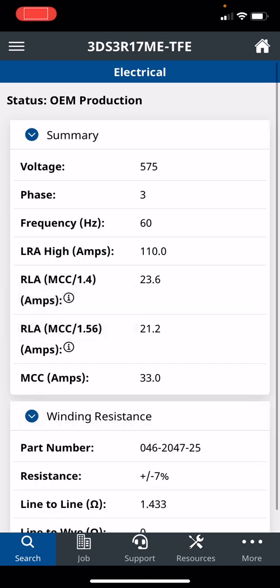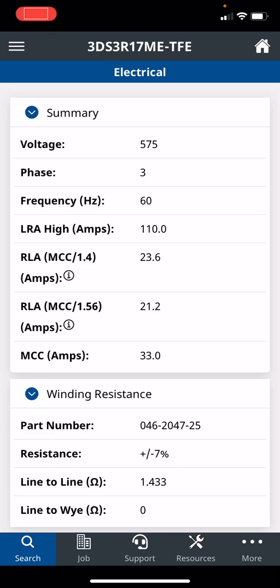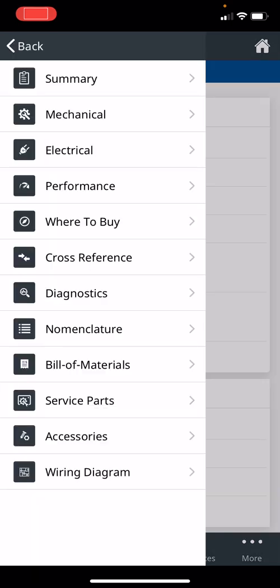Next is the winding resistance. How amazing is this? It's telling you what line-to-line resistance in your windings. This is a three-phase compressor, so you should get 1.4 across each line, 1.4, 3, 3. If you get 1.5, 1.4, then it's fine. Those windings are perfectly fine.